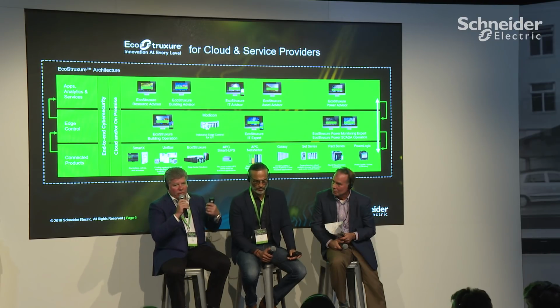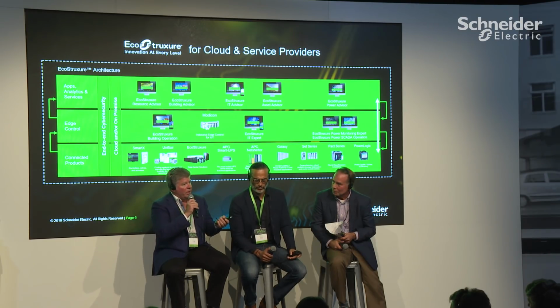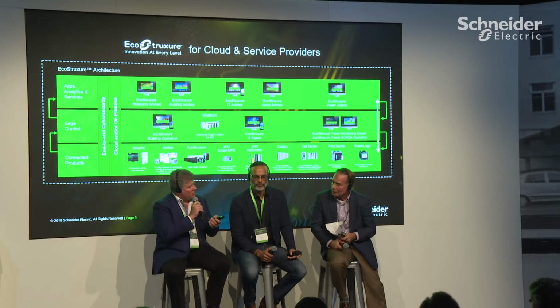When you're building a very large data center, it takes some number of months to fill it, so for a while it's operating at low utilization. So why run all the cooling skids when you only have a tenth of the IT load in there? Why run all the cooling towers at full fan speed? Well, that's just because that's the way they were set up.